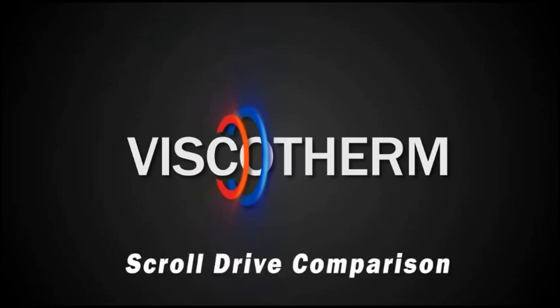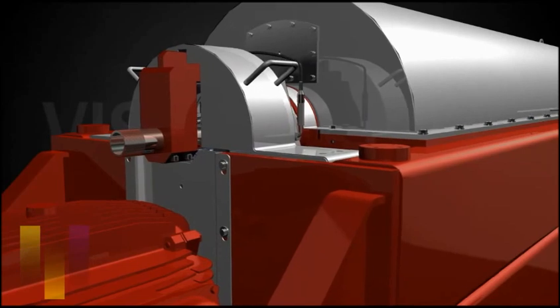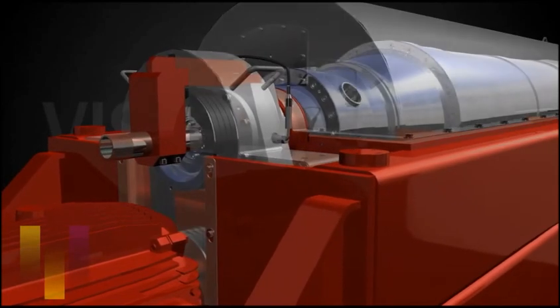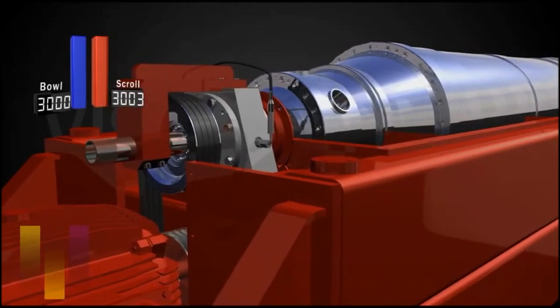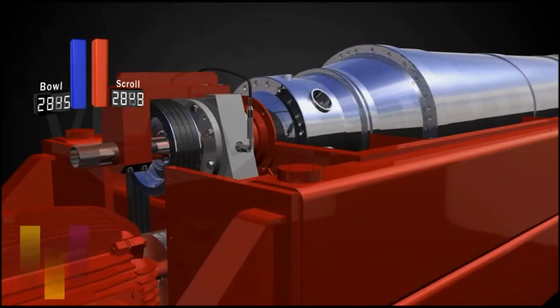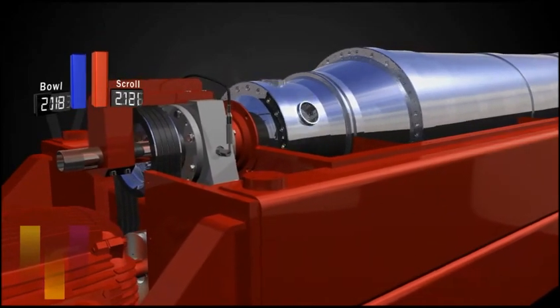Hydraulic scroll drive based on rotative technology versus gearbox drive. The centrifuge bowl is driven by an electric motor or hydraulic motor, normally through V-belts. The bowl speed is adjustable through the use of a VFD.